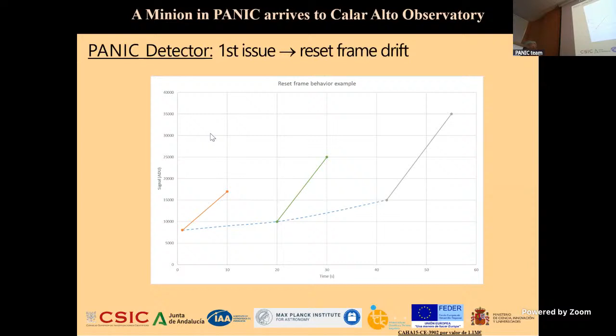What does it have? It has a reset frame drift. What does that mean? As you see on this slide, the blue dotted line is supposed to be the reset. The reset should not change, independent of the light coming and of where it ends. The reset should always be like this. Now, next, please. What happens in reality? The reset increases with light or with time. It is, of course, an intrinsic characteristic of the detector that has to be solved in some way.